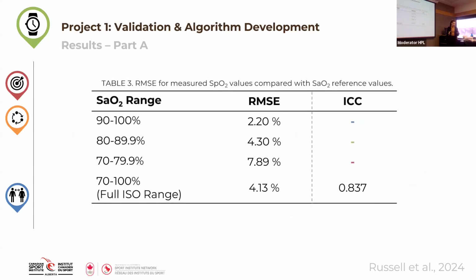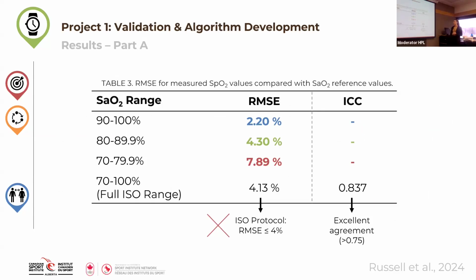Okay, so getting into all our stats. So root mean squared error and ICC. We can kind of see as we go down the root mean squared error, the SaO2 ranges, we start pretty accurate and then it slowly gets worse. So at 70 to 80%, we're at almost like an 8% difference between the SaO2 and SpO2. And so overall, we have a 4.13% difference between the two, which based on the ISO protocol is too high. And then our ICC value is actually pretty good. So it's 0.837, which actually falls into the excellent agreement category. Again, this shows why we had so many different statistical methods, because they all tell a bit of a different story.